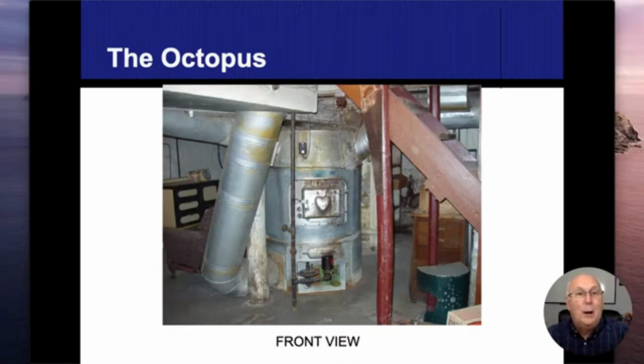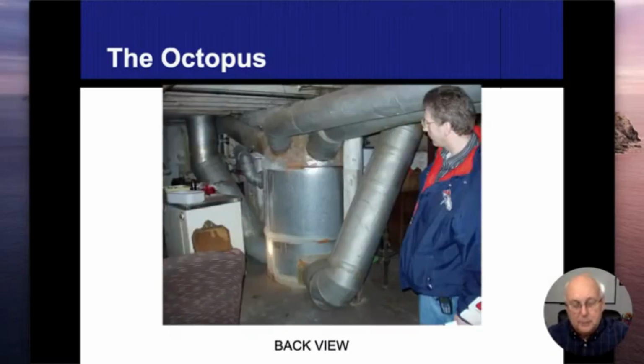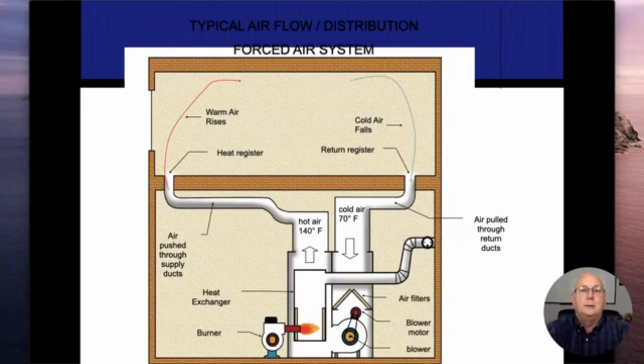Gravity furnace. Now, I know it says Octopus on there, and that's more of a nickname than anything else. And if you look at the ductwork coming out of the top of this one, the actual piece itself kind of looks like the body of a squid and all the legs that are coming off of it. But the real name I want you to know is gravity furnace. No blower fan, nothing but turn fire on, turn it off. No filter. There's nothing to go ahead and get the circulation in.